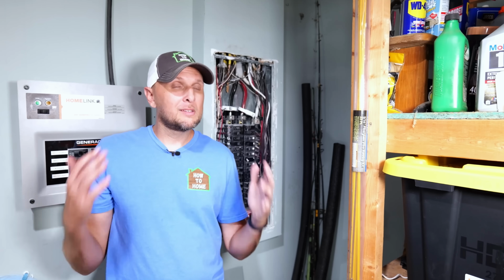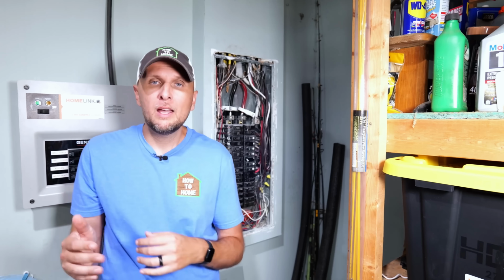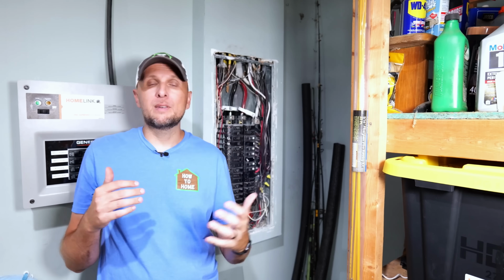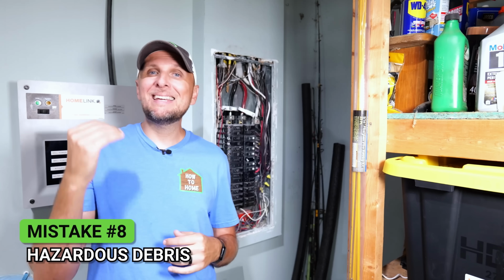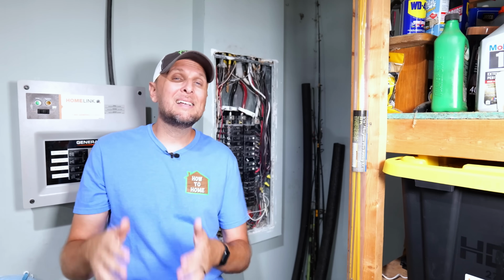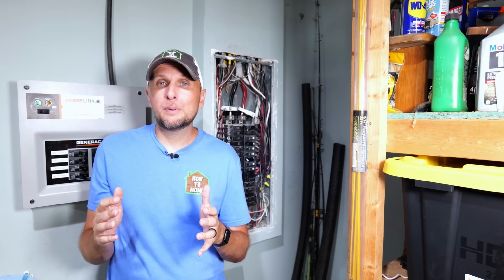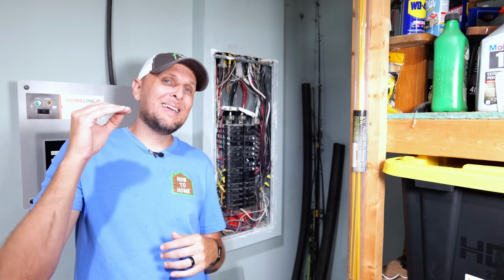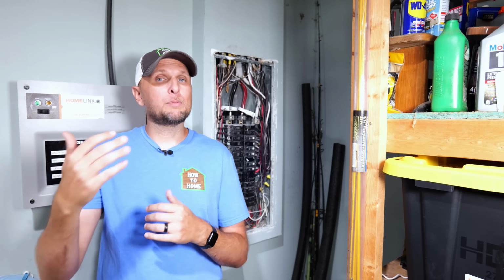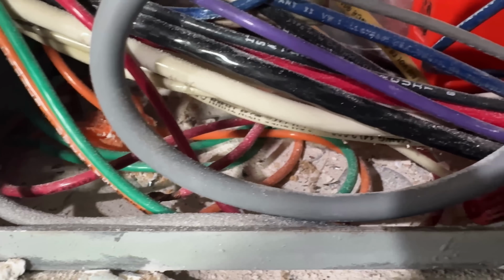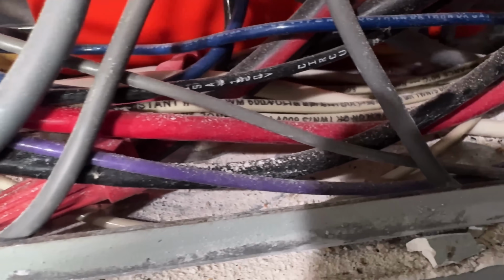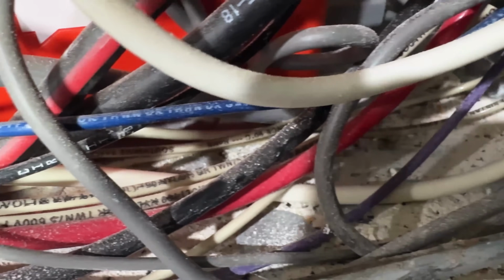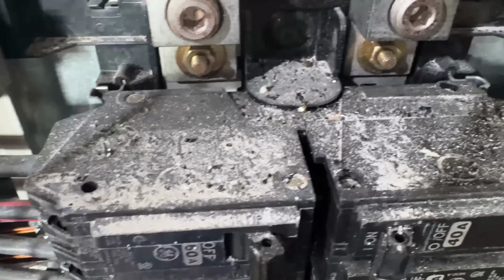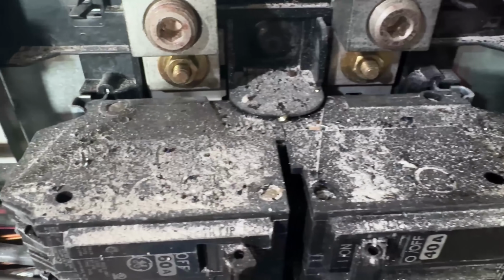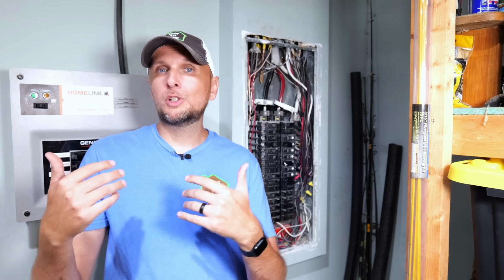This next mistake piggybacks off the last one: allowing debris to get inside your panel. This can pose a serious fire risk, and open slots just invite debris in, which could cause these issues. I've personally seen panels that look like a workshop floor, with combustible material sitting right next to live wires. Honestly, when I open this one up, it doesn't look that much better. So what's the fix, or what should we avoid?